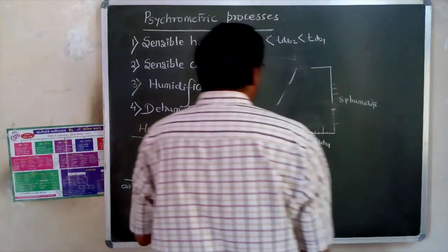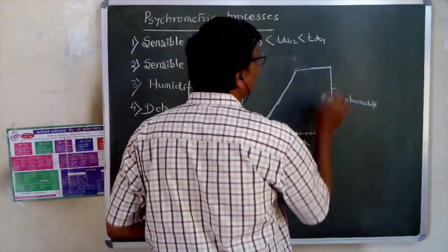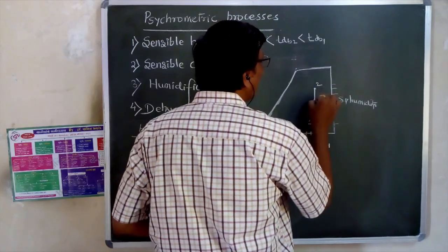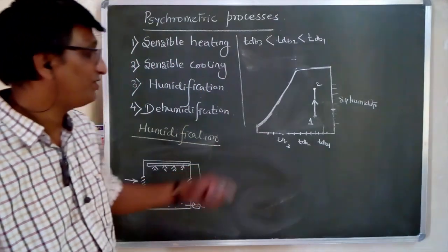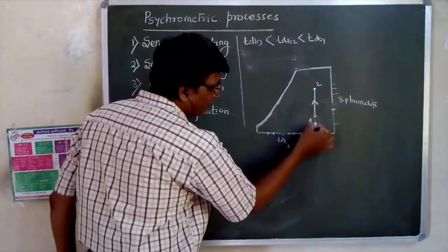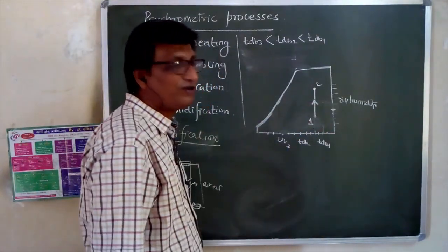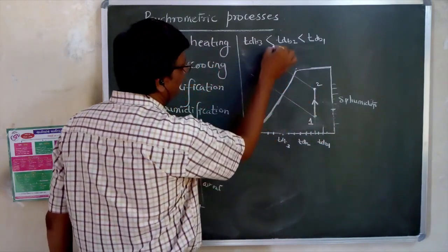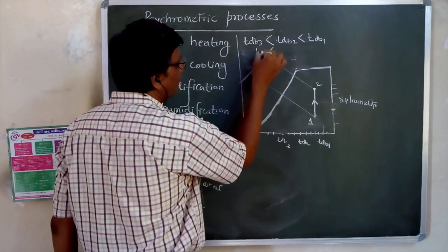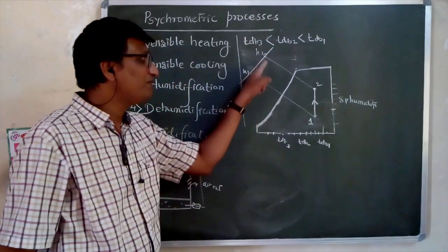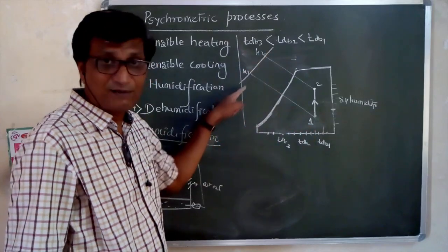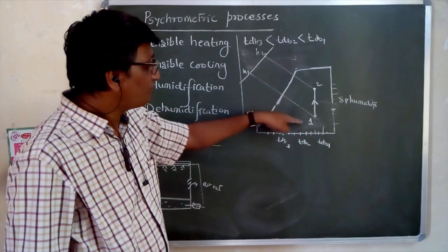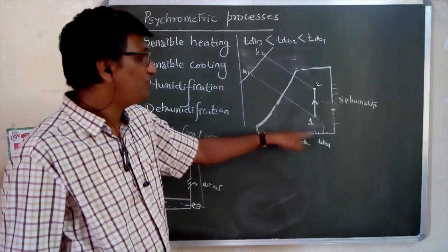On the psychrometric chart, humidification is represented as a vertical line. Point 1 is the initial state and point 2 is after humidification — both having the same dry bulb temperature, so temperature does not change. However, the enthalpies are changing: H2 is greater than H1. So in this process, you get no change in dry bulb temperature but an increase in water content and enthalpy. This is called humidification.